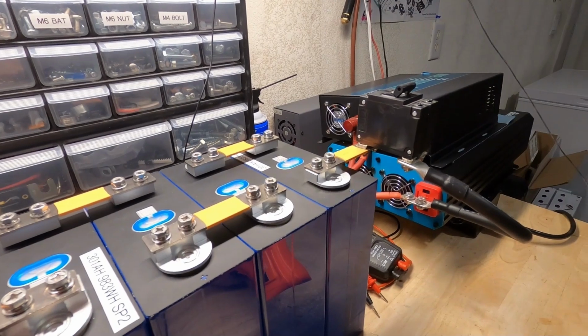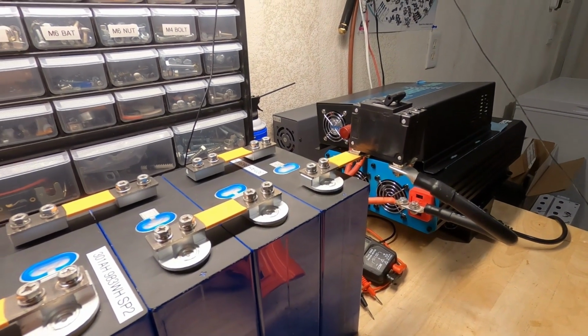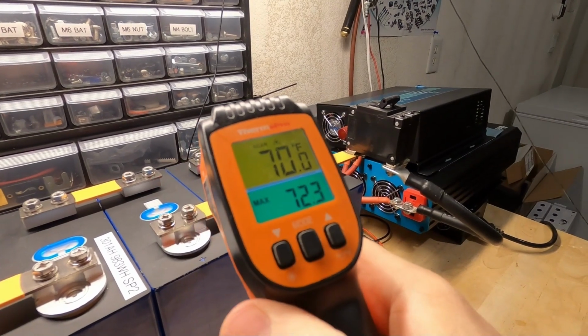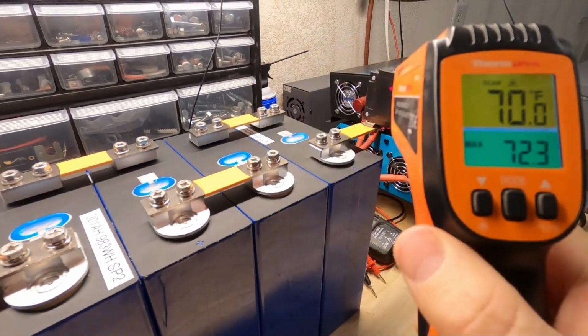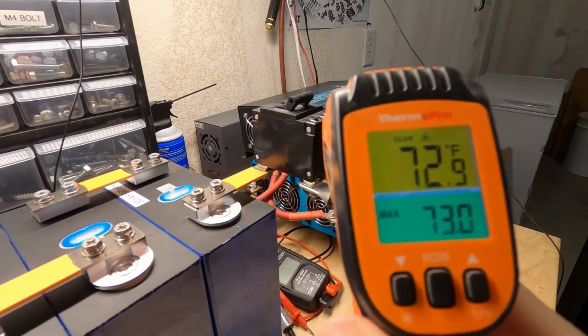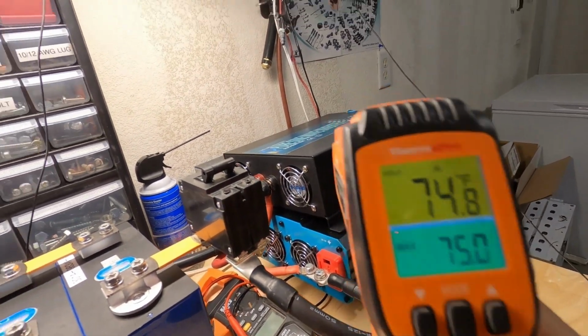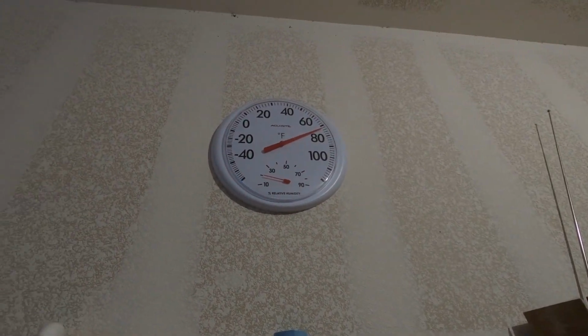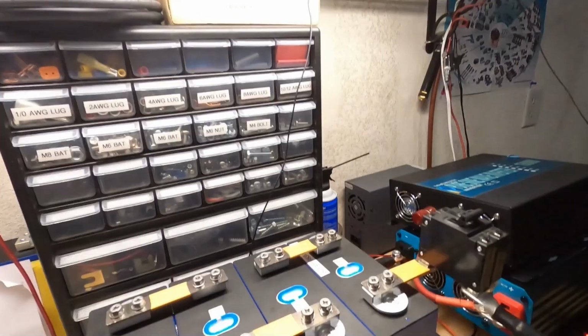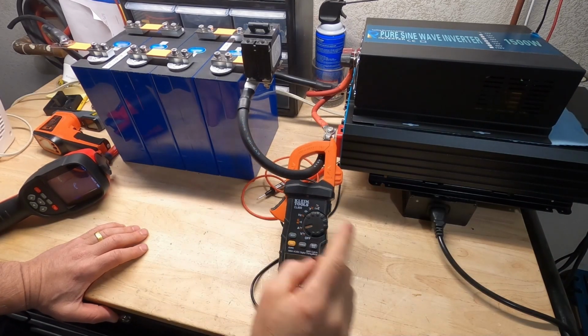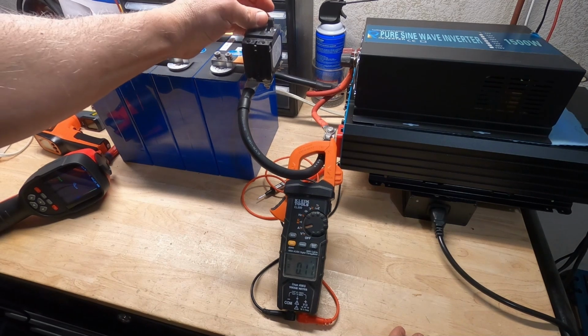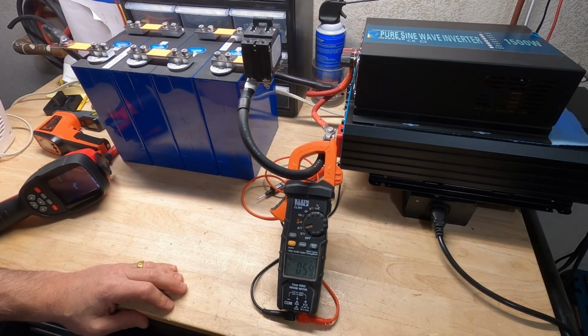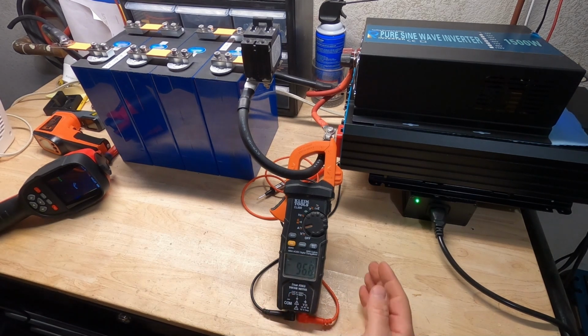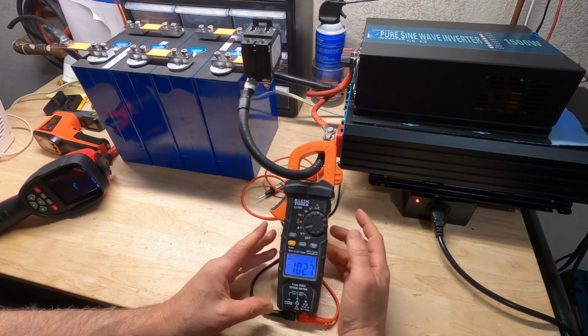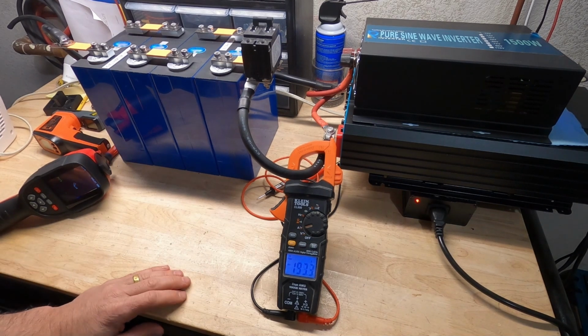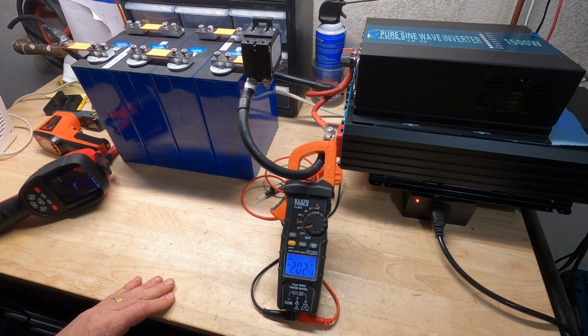Okay, so before we start the factory test, let's do a baseline ambient temp check. So we're looking about 70 degrees on our battery pack. Breakers at 73, inverters at 74, and the room temp is about 72, it looks like. Got the clamp meter on the 50mm cable here. We're going to push about 200 amps. 96 right now, 97. Okay, we're pushing 202 amps right now.